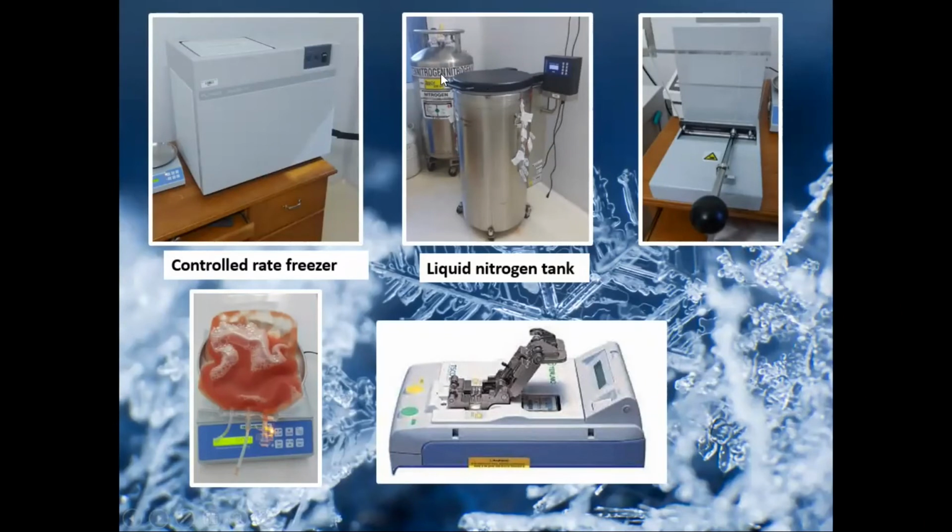This is the additional nitrogen tank which we have for the continuous supply of the nitrogen. This is an additional thing which we have because if the nitrogen in the nitrogen tank goes down, there should be some alarms. For the continuous supply of the nitrogen, we have an additional tank, so this will be automatically filled. This is a manual plasma extractor that everybody will have seen. This is a sterile connecting device or docking device. This is the balance weight which we have for calculating the weight.